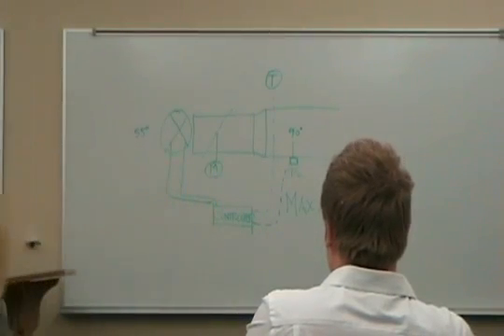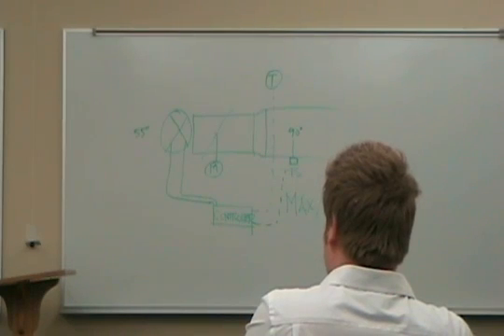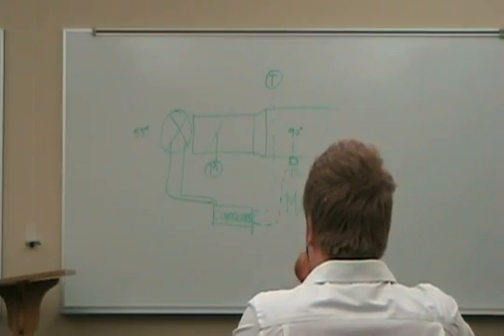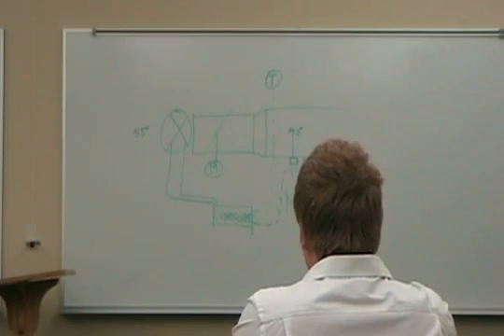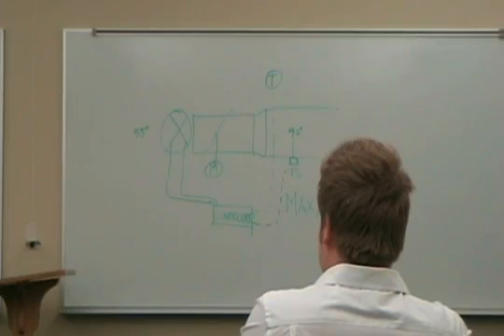But that's a single duct box. It has no reheat. So you can see if my minimum airflow is 100 CFM and I have no reheat, this is pumping out 55 degrees all the time because it's a single duct cooling only VAV system. My heat is dependent in these zones. And that's the purpose for these VAV boxes. They just create temperature zones in the space, control points. So, you might have it per office, you might have it for groups of 3 or 4 offices, you might have a conference room, whatever, but that VAV box is creating a temperature zone in the space.